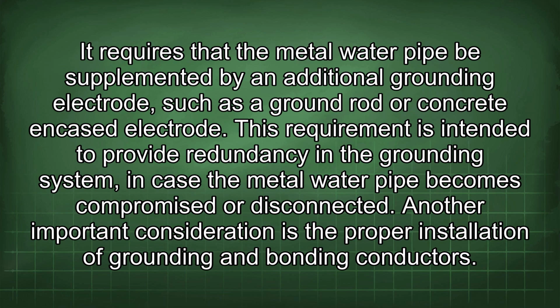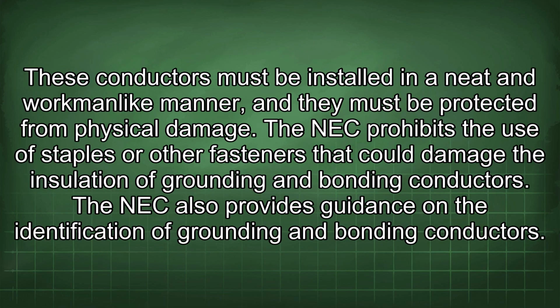Another important consideration is the proper installation of grounding and bonding conductors. These conductors must be installed in a neat and workmanlike manner, and they must be protected from physical damage. The NEC prohibits the use of staples or other fasteners that could damage the insulation of grounding and bonding conductors.